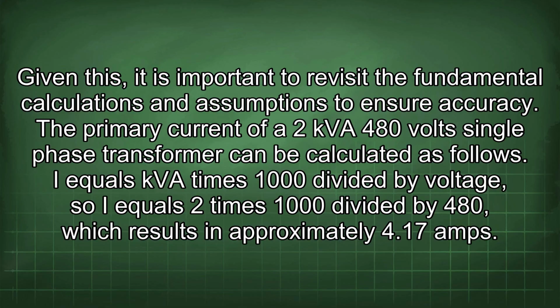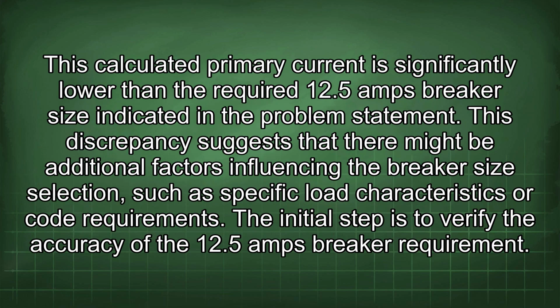The primary current of a 2 kVA 480 volt single-phase transformer can be calculated as follows. I equals kVA times 1000 divided by voltage, so I equals 2 times 1000 divided by 480, which results in approximately 4.17 amps. This calculated primary current is significantly lower than the required 12.5 amps breaker size indicated in the problem statement.